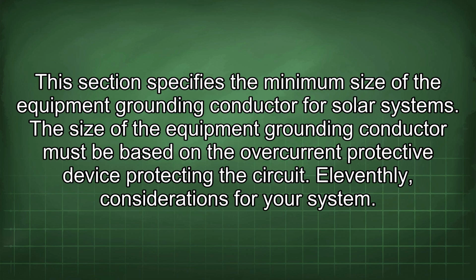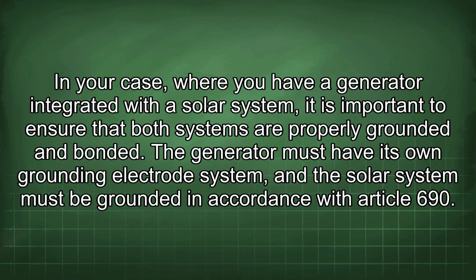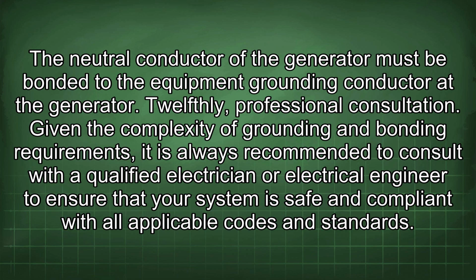11th, considerations for your system. In your case, where you have a generator integrated with a solar system, it is important to ensure that both systems are properly grounded and bonded. The generator must have its own grounding electrode system, and the solar system must be grounded in accordance with Article 690. The neutral conductor of the generator must be bonded to the equipment grounding conductor of the generator.